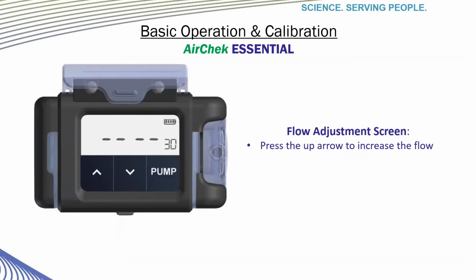Now that you've got your calibration train set up and ready to go, at this point you would use the up or down arrows to adjust the flow to the flow rate. Now remember, this is a basic pump and so it does not display flow rate. That's why we've given you the flow indicator just to give you an idea. So at this point you're making this adjustment. You are looking for your desired flow rate to be displayed on your calibration device. For this presentation purposes, we're going to press the up arrow to increase the flow rate.